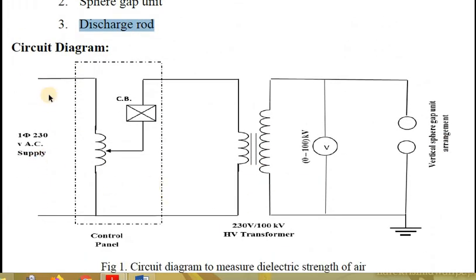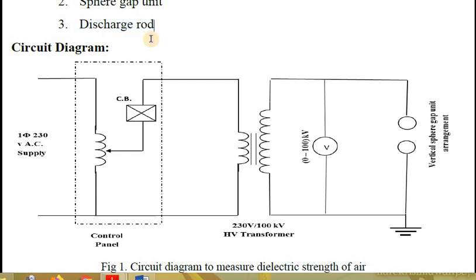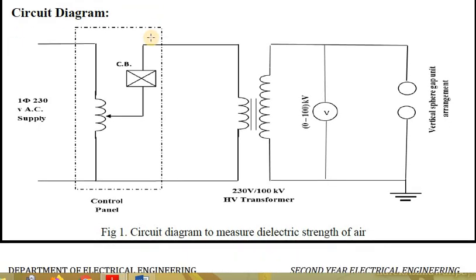Here is the circuit diagram to be followed. We need a single phase AC supply of 230 volt, 50 Hz. This AC supply is connected to a single phase autotransformer, also called a single phase variac. Through this autotransformer, it is connected to a circuit breaker, and from the circuit breaker it is connected to a step-up transformer rated 230 volt to 100 kilovolt. At the secondary side, we place the sphere gap unit, with one terminal earthed. The breakdown voltage is measured across the voltmeter, which has a range of 0 to 100 kilovolt.